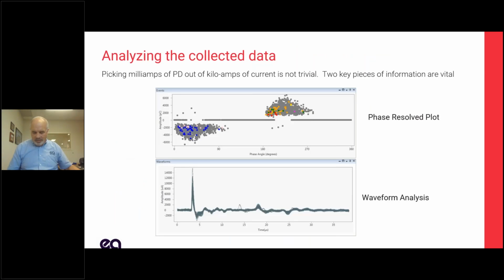When we look at the data, there's a variety of information that we use. This is a phase resolved plot, which shows us each dot is an event that occurs and where it occurs on the sine wave. The bottom is a waveform of the actual current pulse. This is the actual current being generated by the PD. And so we can see that we've got some stuff in the negative half cycle, we've got some stuff in the positive half cycle, the peaks, and my waveforms look like PD should look like. That's real PD.